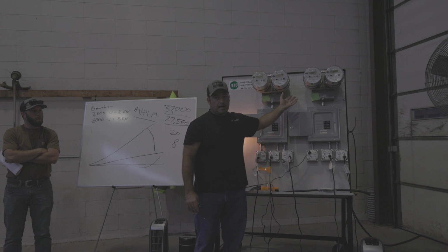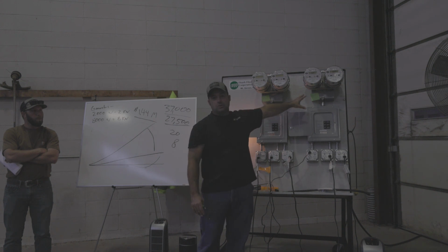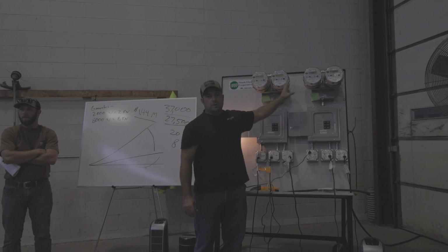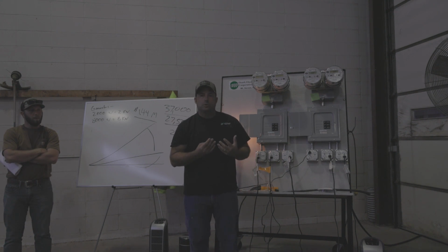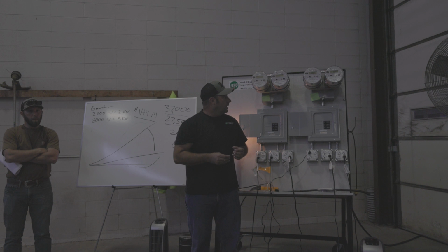KWH doesn't burn things up. Load does. That's KW. That's the capacity you're asking for that meter base to provide. In a 100 amp meter base, it's melted the jaws and the member has to replace that base. So that's an example I want to show you. That's the demand you're putting on your system. That's what matters, the amount of load.